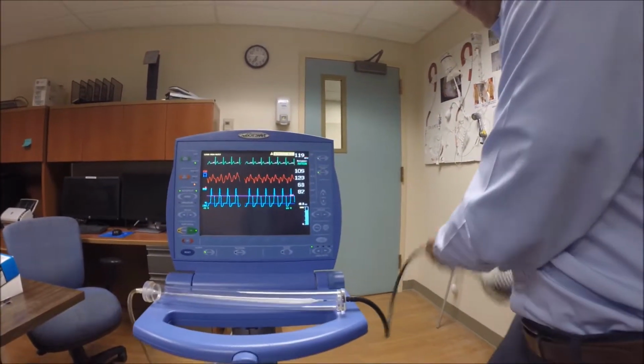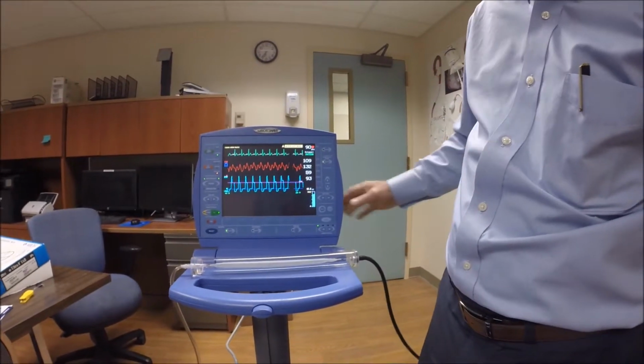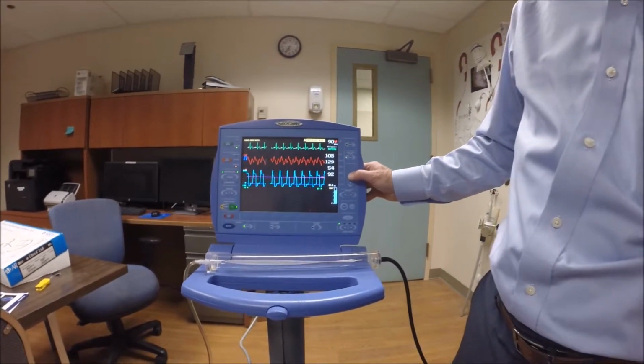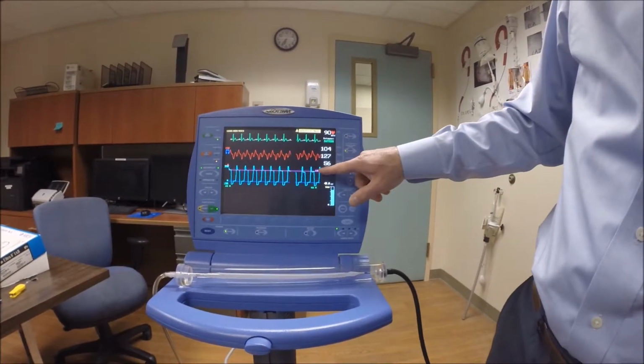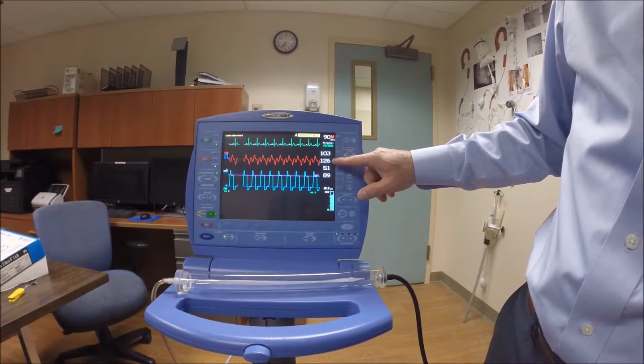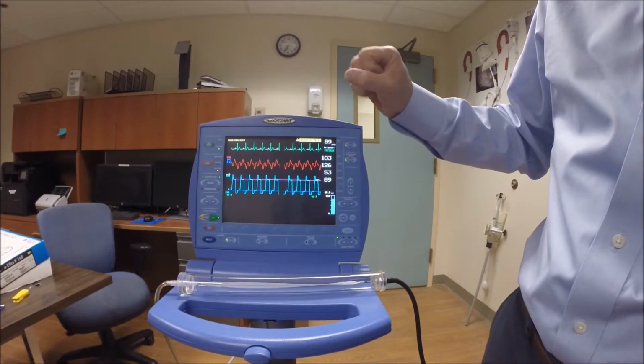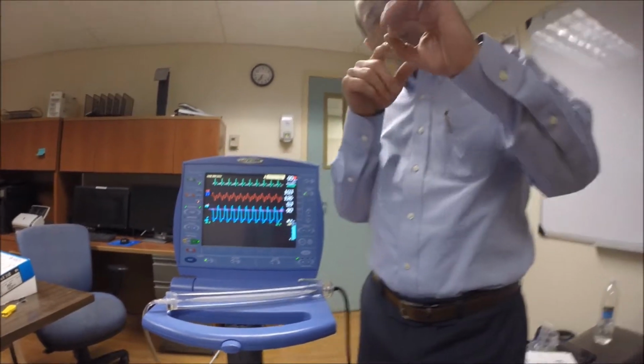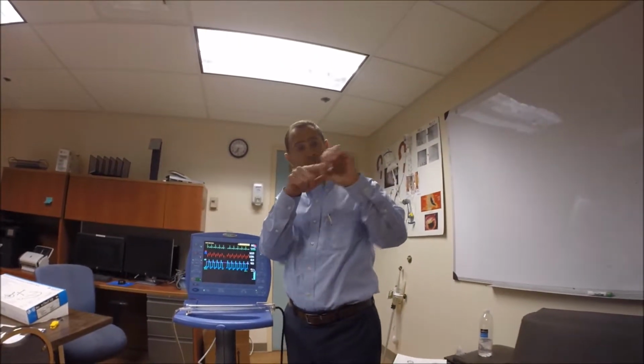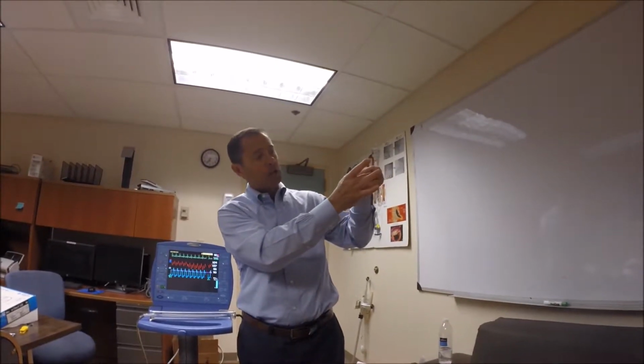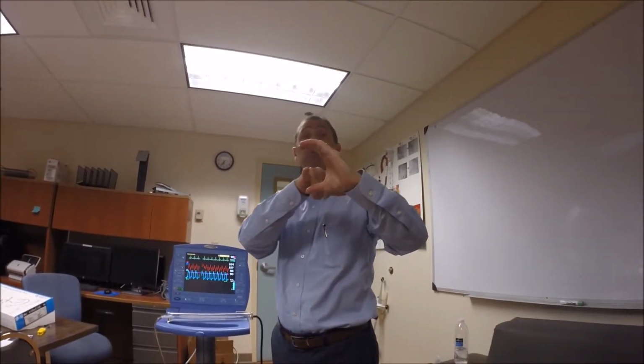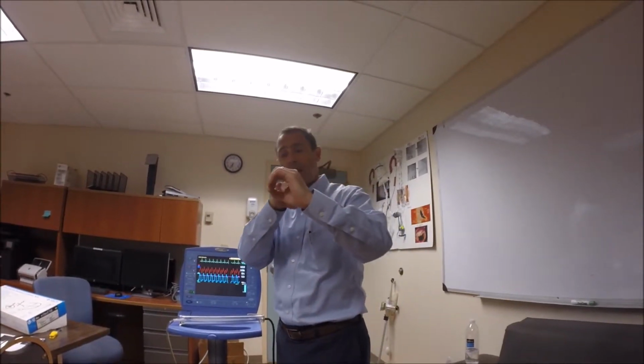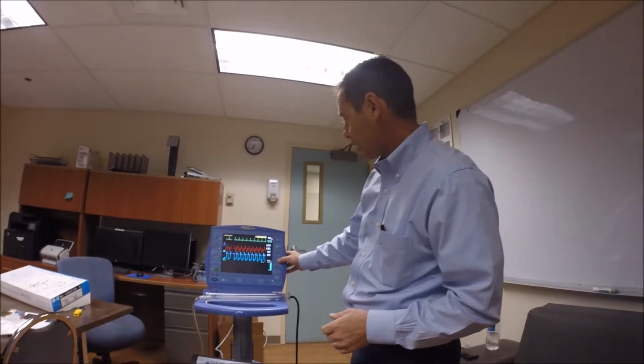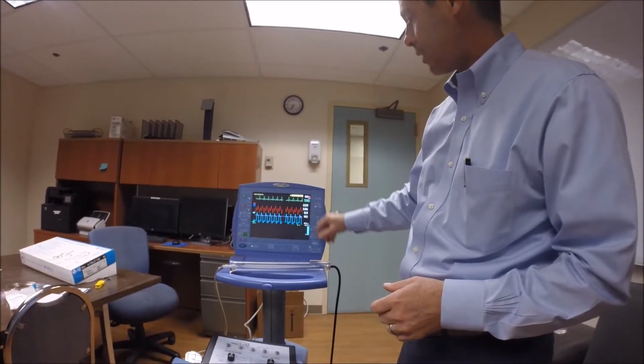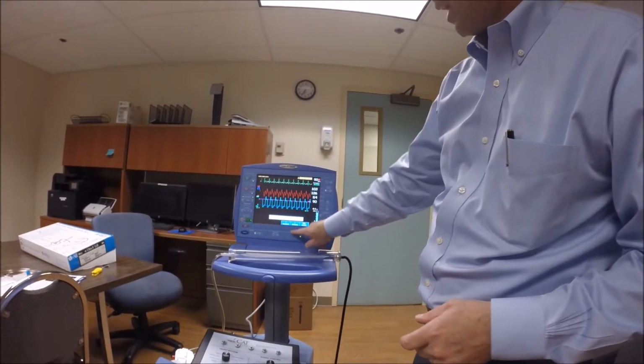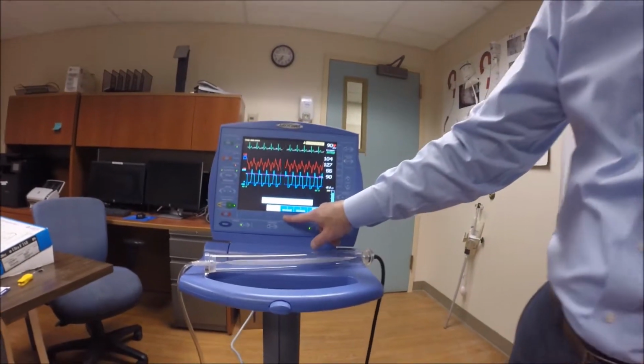However, if I drop that cursor down onto this plateau pressure that was up here, I'm outside of that range, 181 versus 126. It means I have too much pressure on that balloon. If you recall, I only want to occlude that lumen to about 85%. Anything tighter than that, and I may be hitting the inside of that lumen. I certainly don't want it to be too small because I'm not giving them any augmentation, any therapy. So if my cursor comes down onto a number that's outside of that range, I need to go to balloon volume and decrease volume out of that balloon.